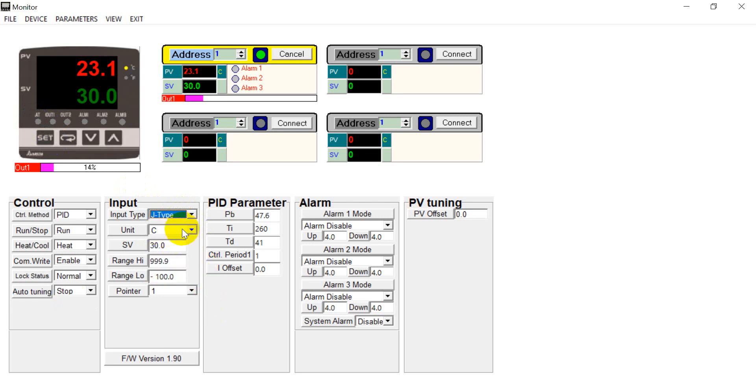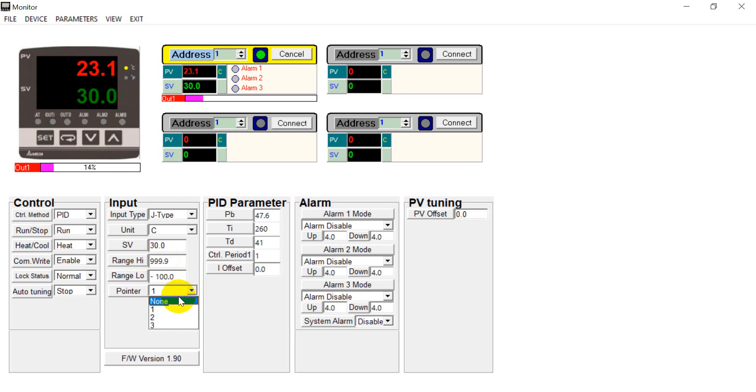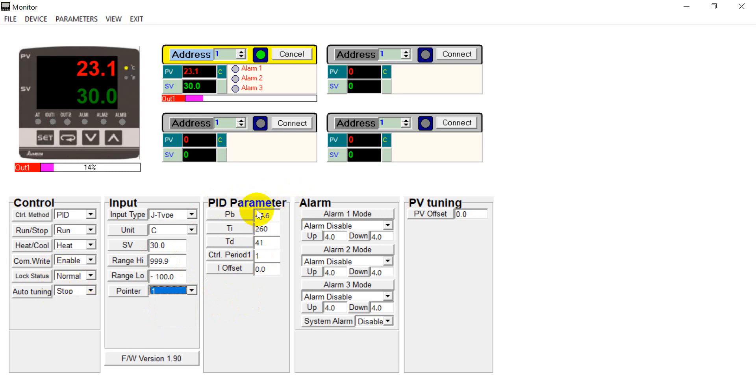And you can also select the different sensor type over here. And for the unit we already demonstrated from Celsius and Fahrenheit. And then you can also check the set value. And here's the range. And the decimal point. Then this is the PID parameter. This value will generate when you use the auto-tuning.